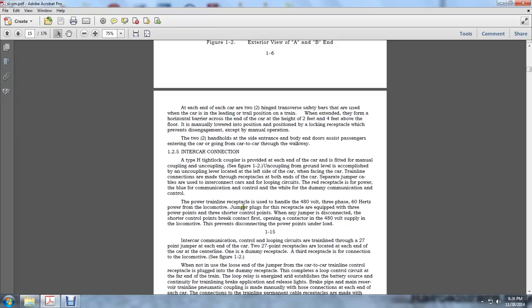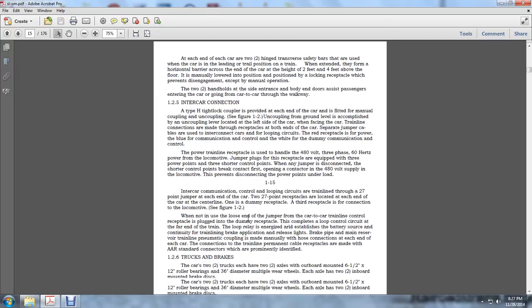Power from the locomotive comes through jumper plugs from the receptacle, equipped with 3 power points and 3 shorter control points. When the jumper is disconnected, the shorter control points break contact first, opening the contactor to the 480 volt supply from the locomotive, preventing disconnection of the power points under load.